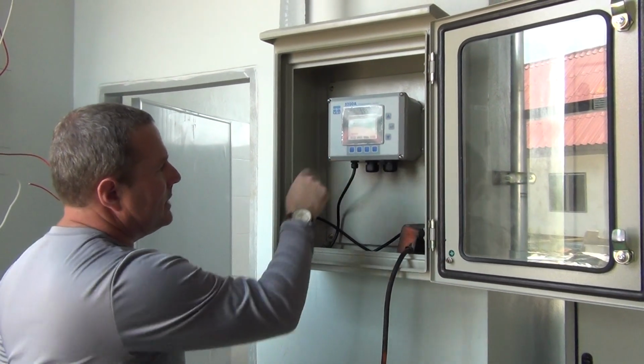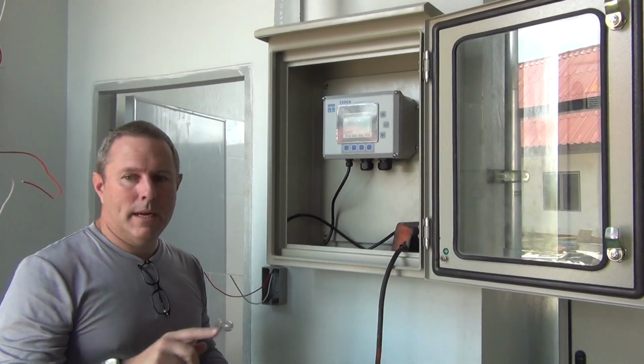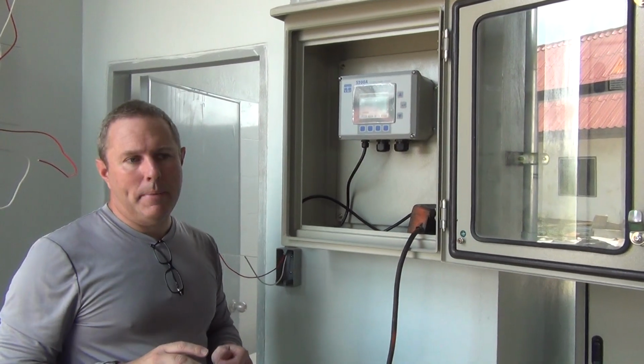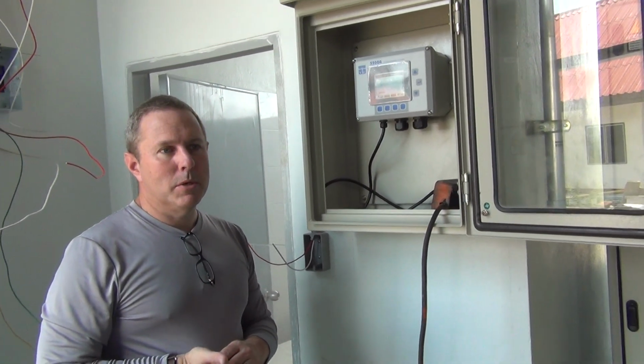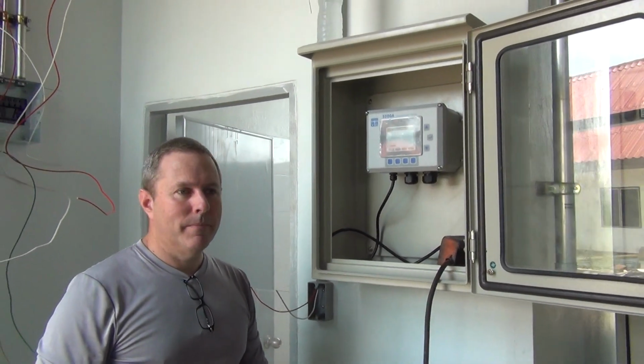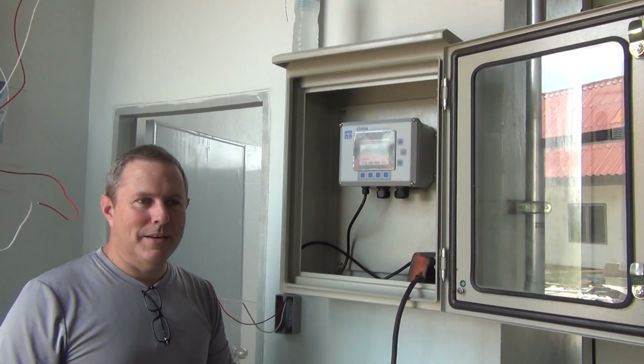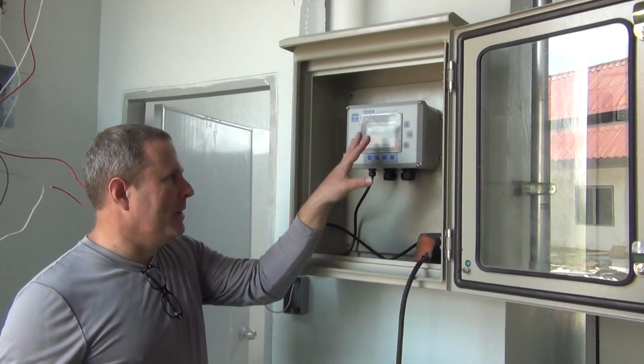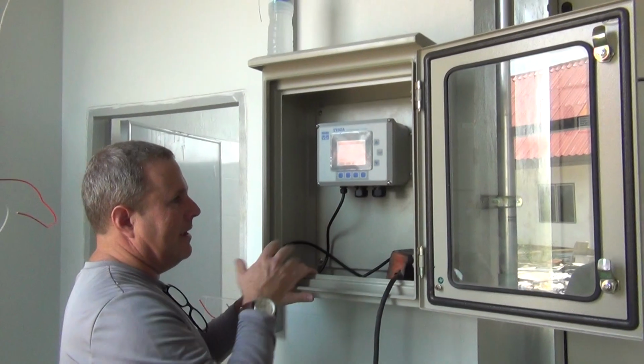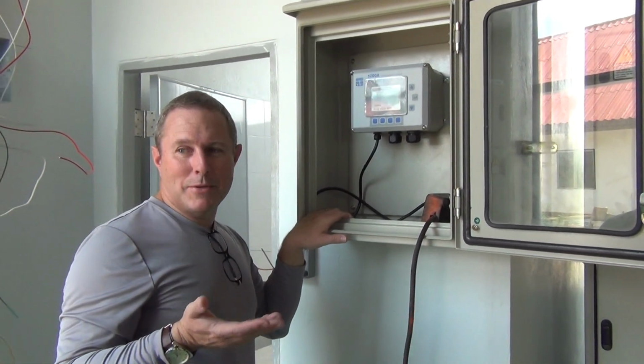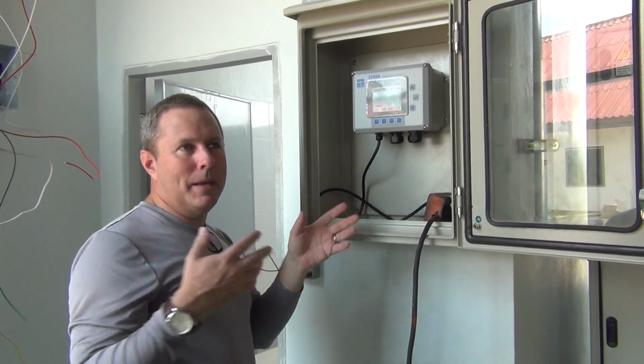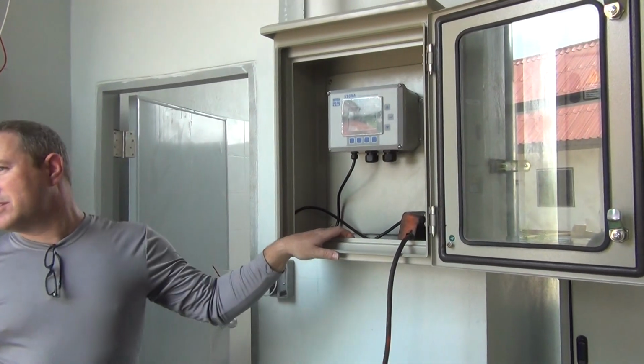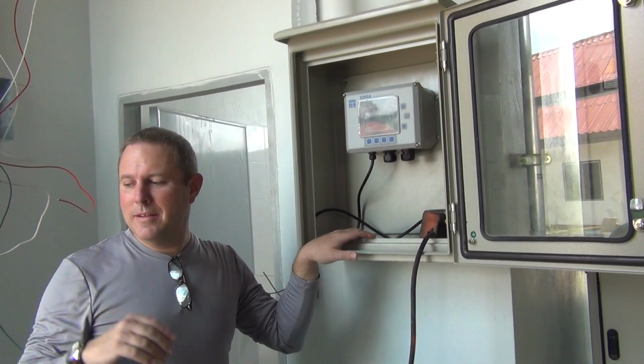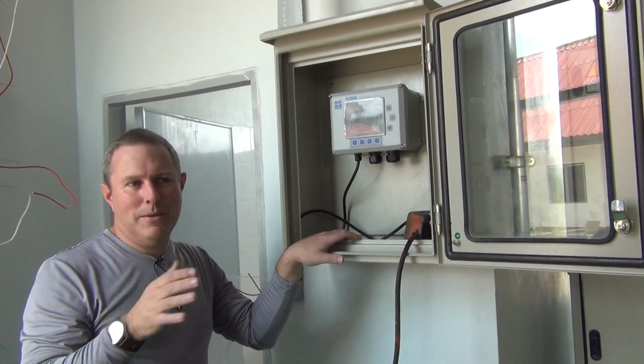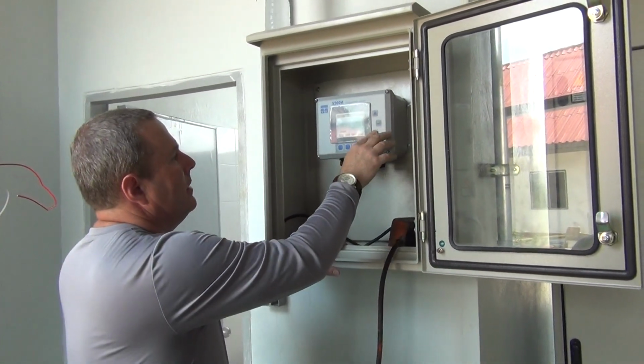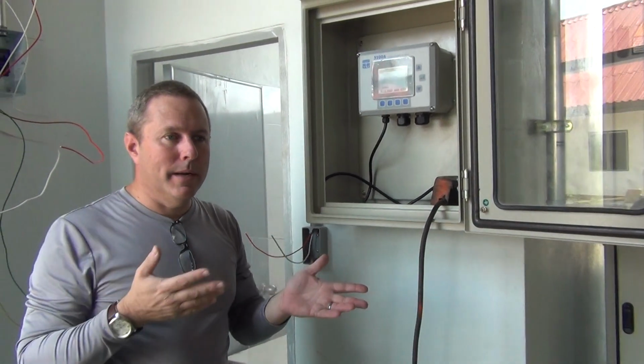And then next is password. This has the ability to set a password where nothing can be done without the password. The problem with that is most people who set the password forget what the password is very quickly, or they'll write it down and lose it. I leave it to you to decide, but this is where you would put in your password. I personally don't advocate putting a password in unless there's going to be easy access to the outside. But it looks like you're going to have a door that locks and nobody's going to be coming in and out and messing with it, so I would not worry about it. But if you choose to set a password, I can do it. Do you wish a password?